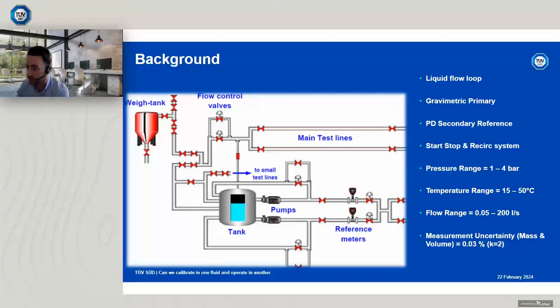The uncertainty for a primary gravimetric system is 0.03% for mass and volume at K equals 2, and our secondary reference, so these positive displacement meters that are pre-calibrated against our weigh tank for temperature, pressure, flow rate and viscosity, they nominally have an uncertainty of 0.08% for fluids below 50 centipoise. For fluids greater than 50 centipoise, the uncertainty is 0.25%.